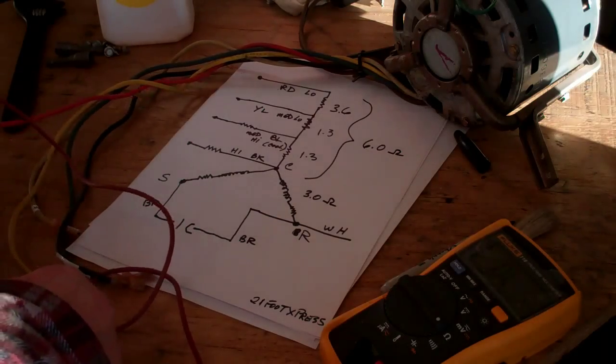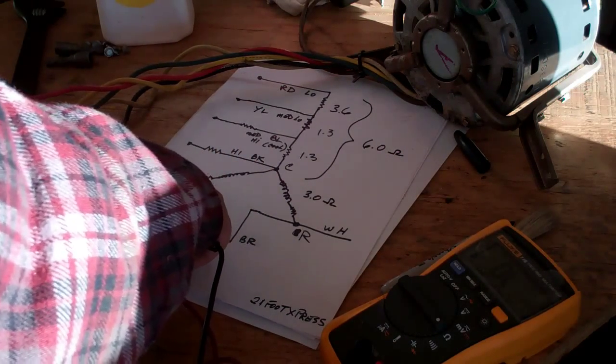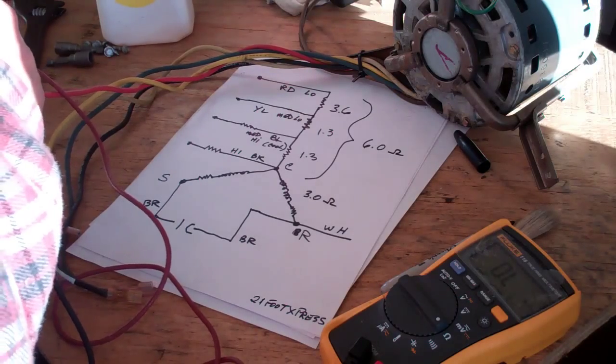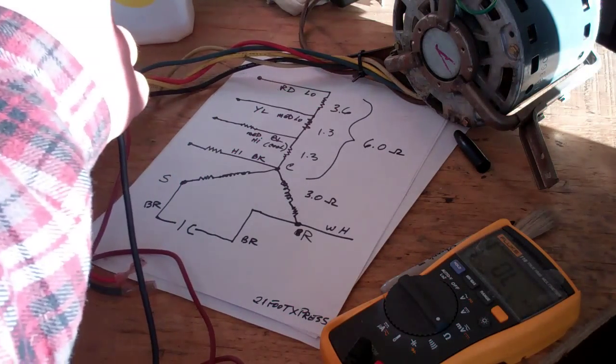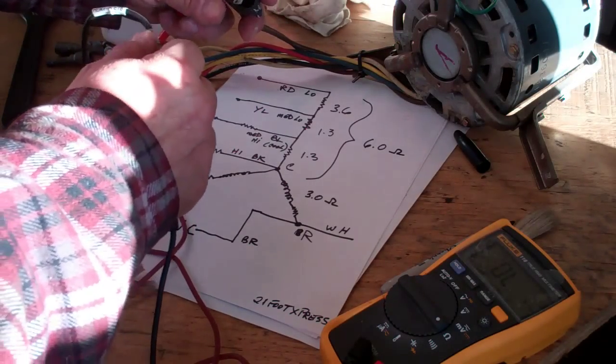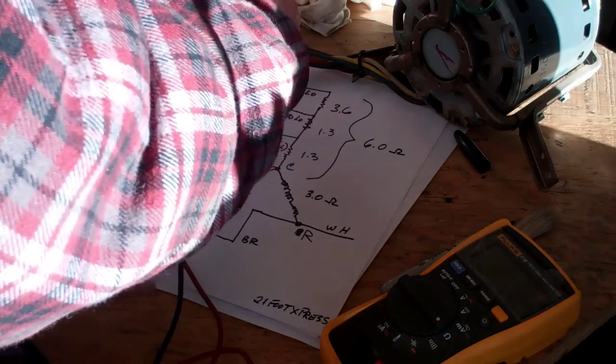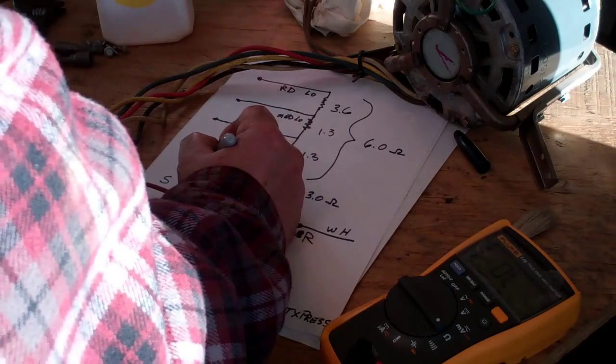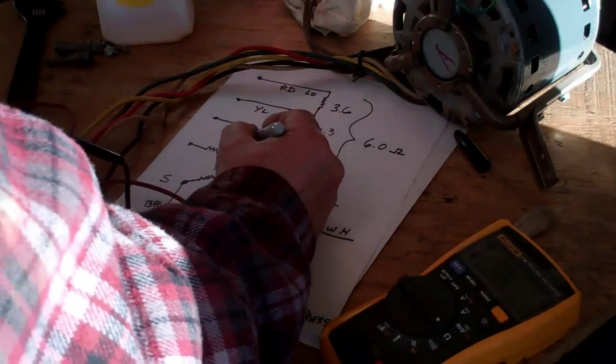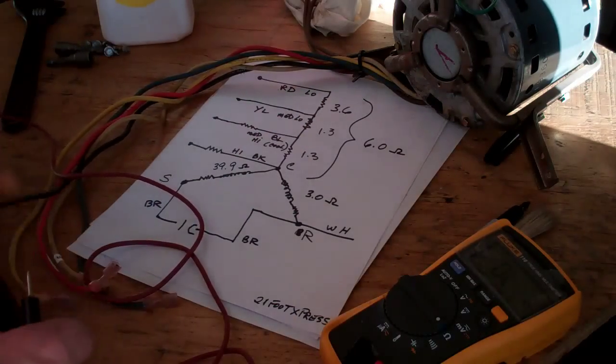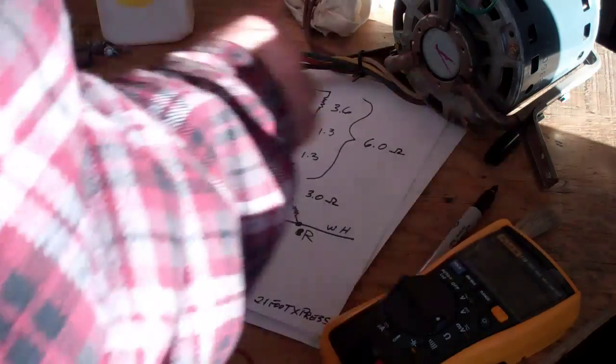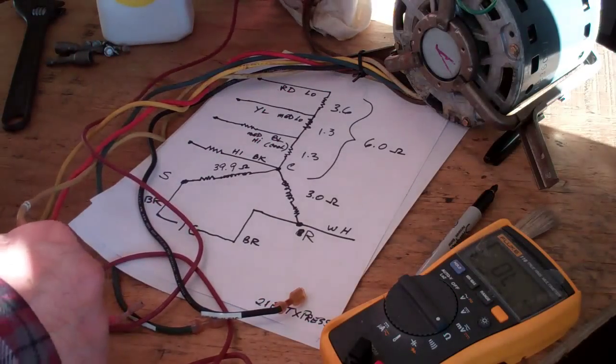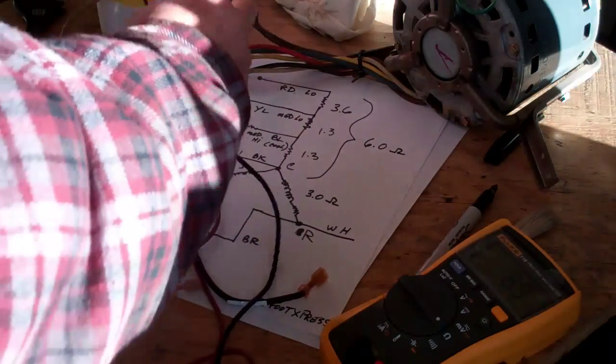And then I want to go check this winding now and check from black to the start terminal which is one of the brown leads. There's two brown leads. There's 39.9 ohms.